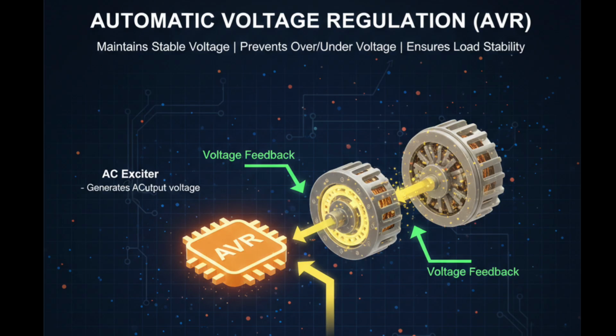The automatic voltage regulator, AVR, is the brain of the brushless excitation system. Take a look at the slide graphics. The AVR is connected to the stator and rotor, with feedback loops clearly illustrated using animated arrows. The AVR continuously monitors the stator output voltage. If the output drops below the desired value due to load increase, the AVR increases the DC excitation to the rotor.